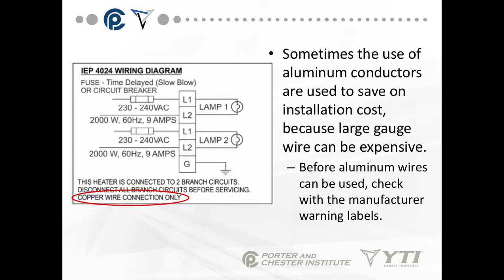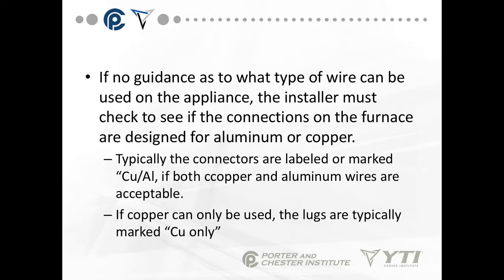Sometimes the use of aluminum conductors can save on the installation cost because large gauge wires can be expensive. However, make sure you check the manufacturer warning labels. Aluminum wire in many cases does not stand up to the heat generated by the large current draws. If there is no guidance as to what type of wire can be used on an appliance, the installer must check to see if the connections on the furnace are designed for aluminum or copper. Typically, the connectors are labeled or marked CU/AL if both copper and aluminum wires are acceptable. If only copper can be used, the lugs are marked CU only.